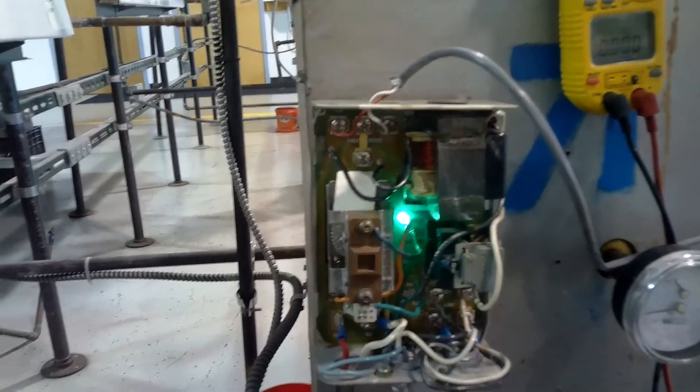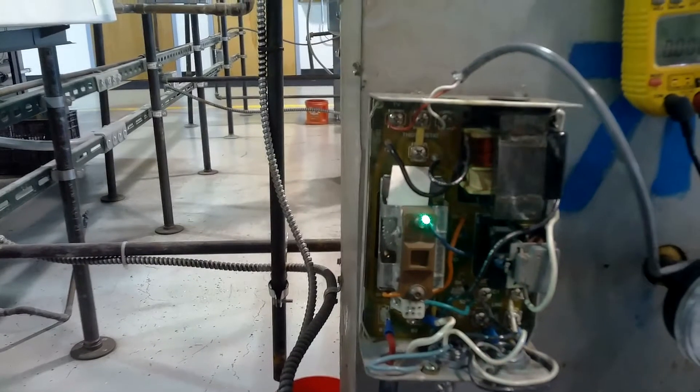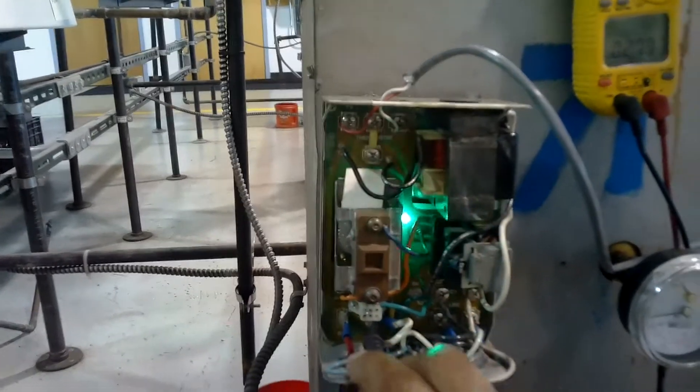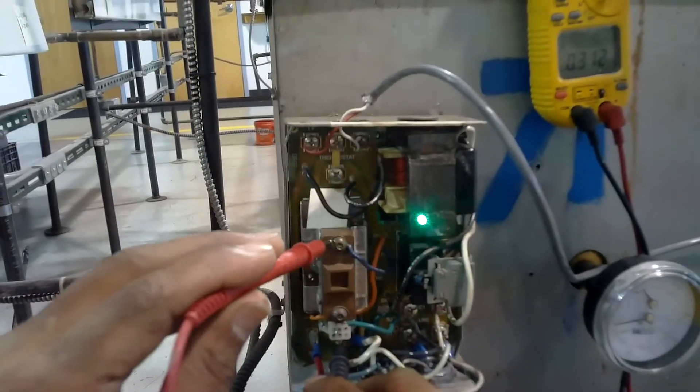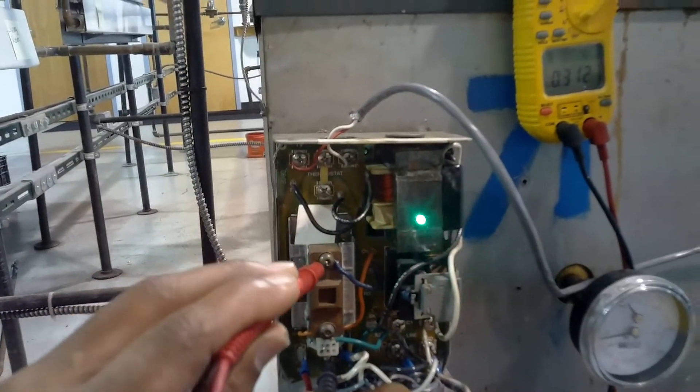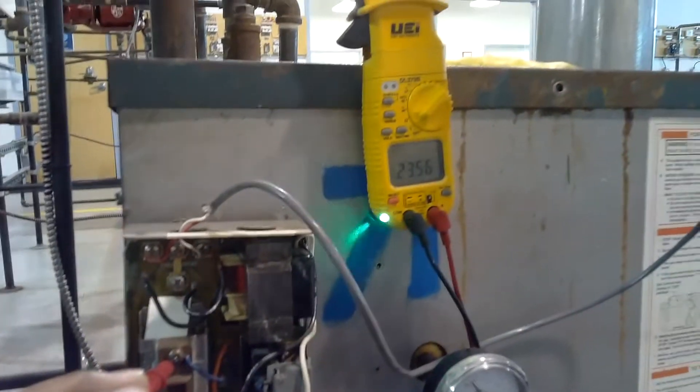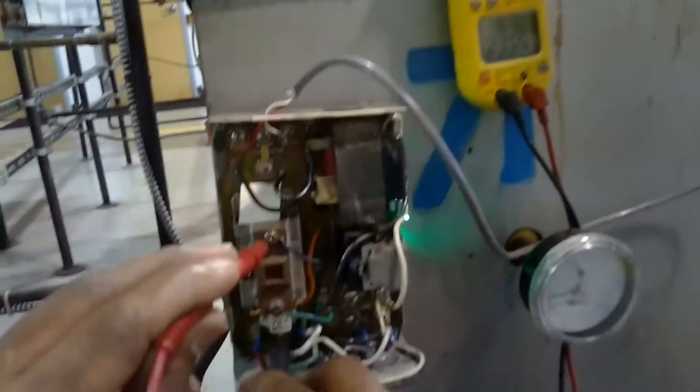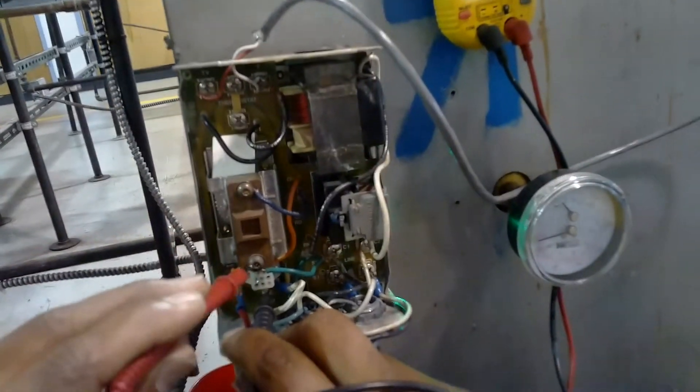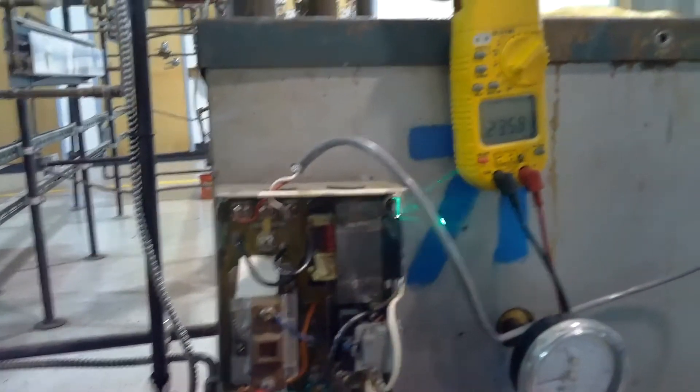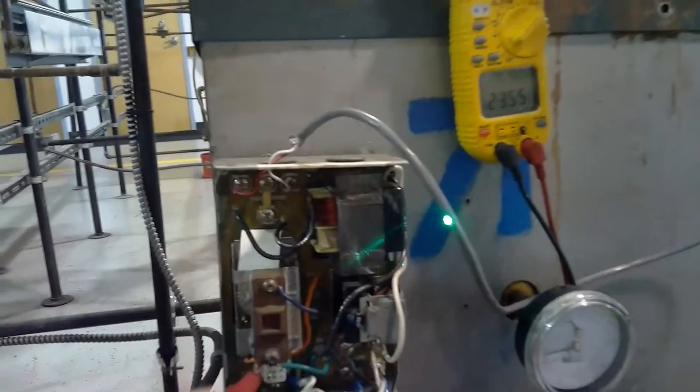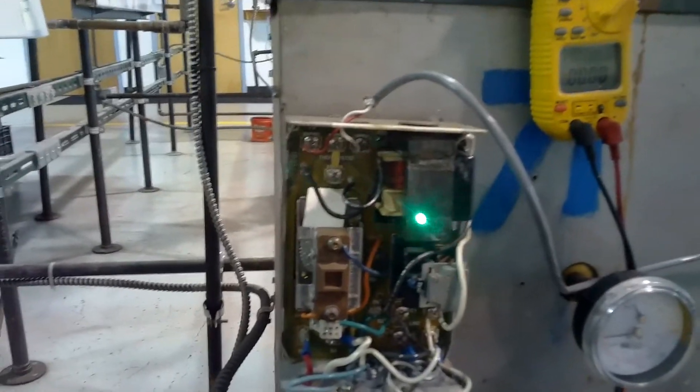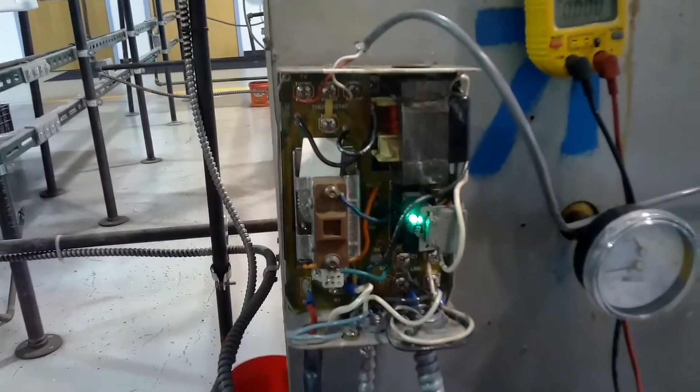Let's see here. 24 volts coming out of my limit, 23 volts. So this is a good working aquastat. Thank you.